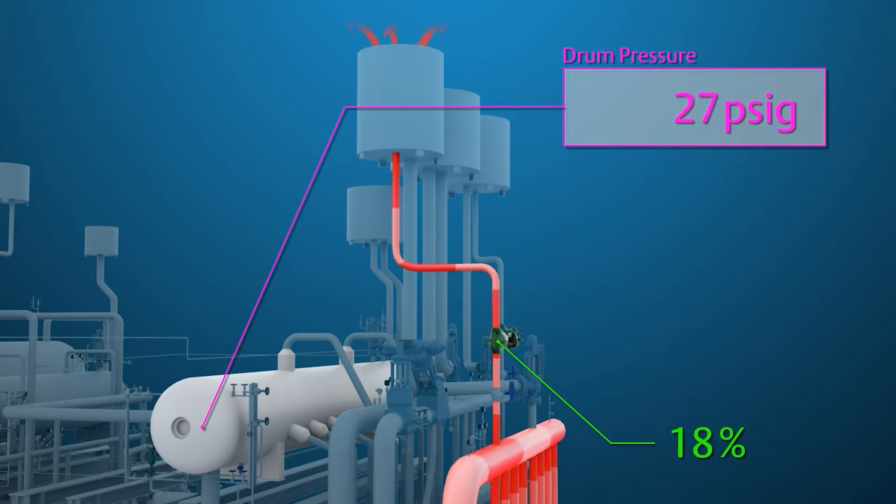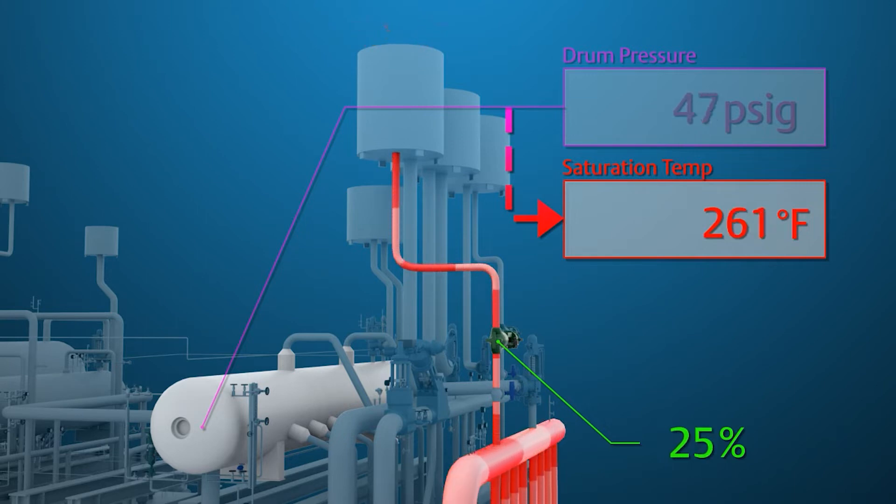The control system logic will calculate the saturation temperature of the steam drum based on the sensed pressure. This is the temperature that is used to control the sky vent valve.